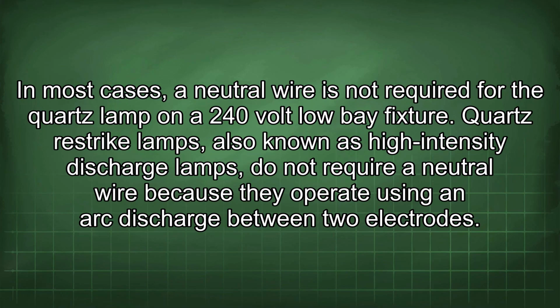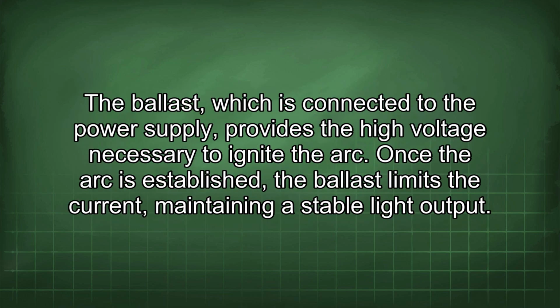In most cases, a neutral wire is not required for the quartz lamp on a 240-volt low-bay fixture. Quartz restrike lamps, also known as high-intensity discharge lamps, do not require a neutral wire because they operate using an arc discharge between two electrodes. The ballast, which is connected to the power supply, provides the high voltage necessary to ignite the arc. Once the arc is established, the ballast limits the current, maintaining a stable light output.